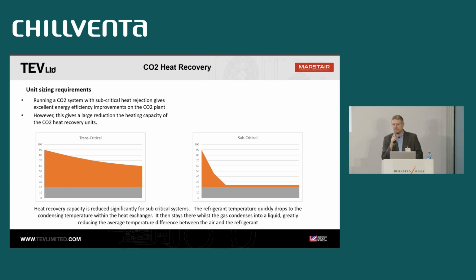So when you're sizing a system, you have to think about the fact that when you need heating, it will probably be when the external ambient is at its coolest. So when you're sizing the system, you have to think about whether the system will go subcritical, and how much duty I will achieve at that particular point. You may be able to artificially keep it transcritical, but is that really running the system at its most efficient in terms of energy efficiency and what you're trying to achieve on the cooling side?